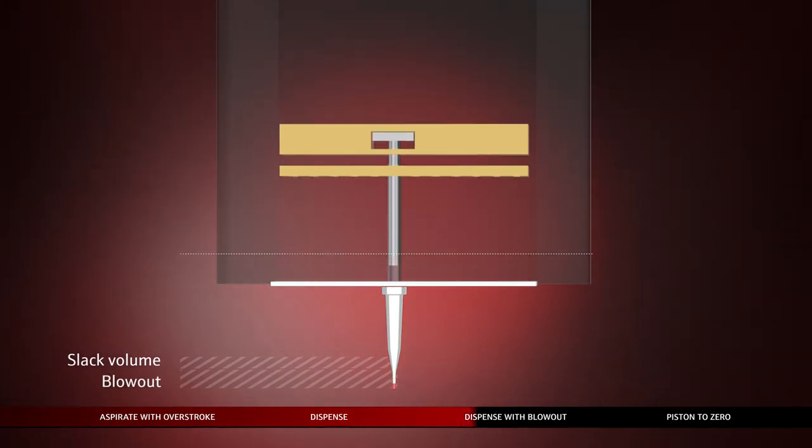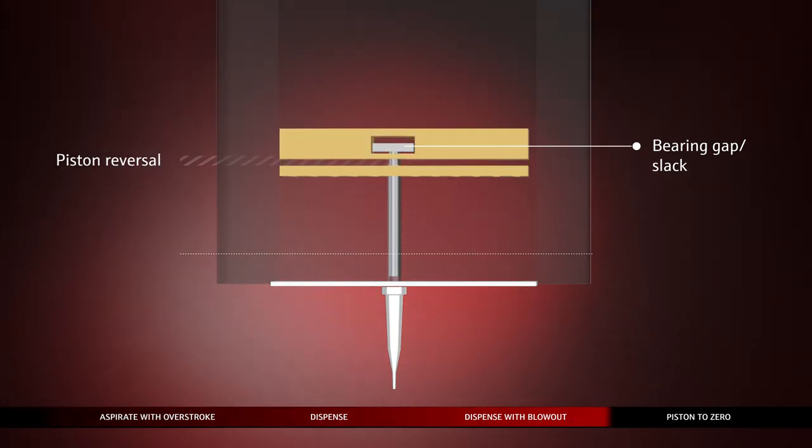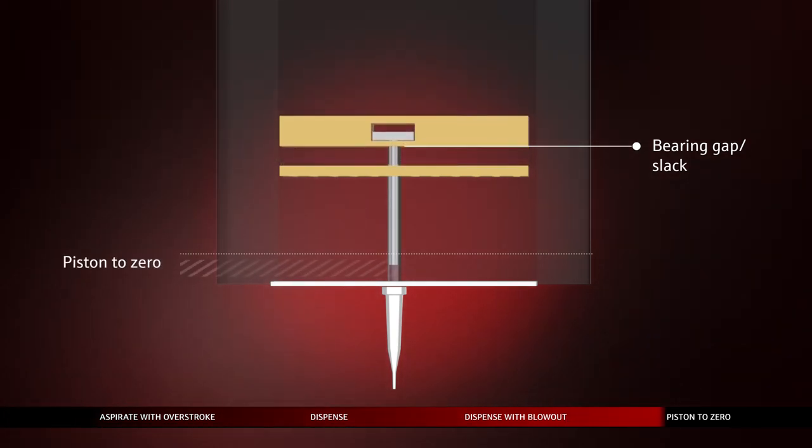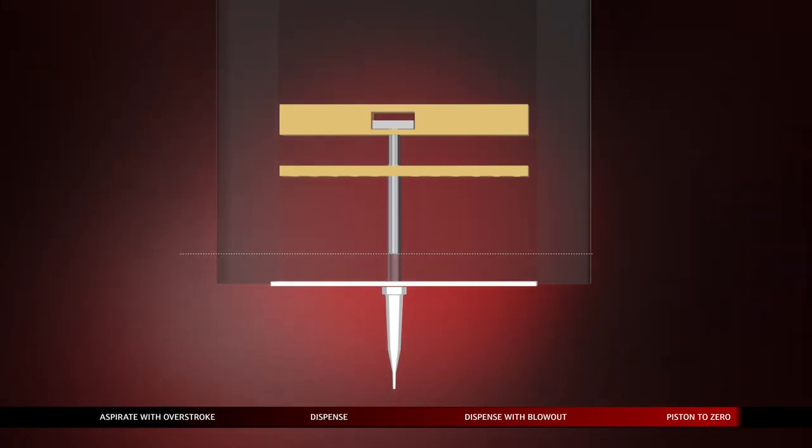The additional overstroke volume and the blowout volume is then transferred back to the source or into the liquid waste. The tips are empty and the pistons move back to the piston to zero line, the starting position, to be prepared to start a new piston cycle.